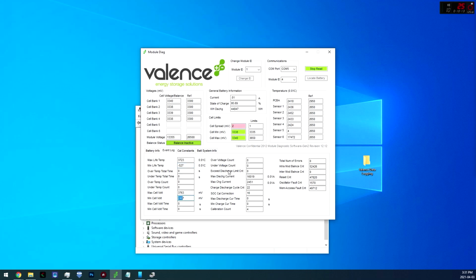Moving over here, max discharge current, 16,000 times 0.01, so that would be 160 amps discharge current, and 24 amps maximum charge current. Charge discharge cycle count, so this is how many times the battery has been fully charged and fully discharged. Well, relatively fully charged and fully discharged. However, whatever this system counts as fully charged and fully discharged, to count it as a cycle count, that is what it is. I'm assuming probably 80% charged to 80% discharged, probably just to give or take.